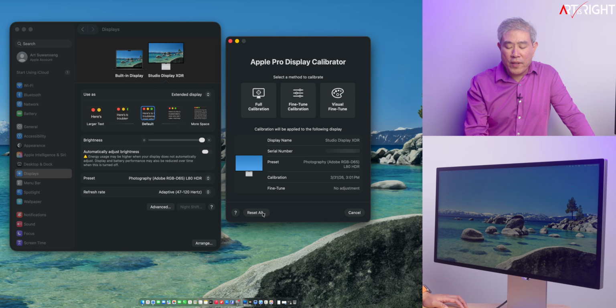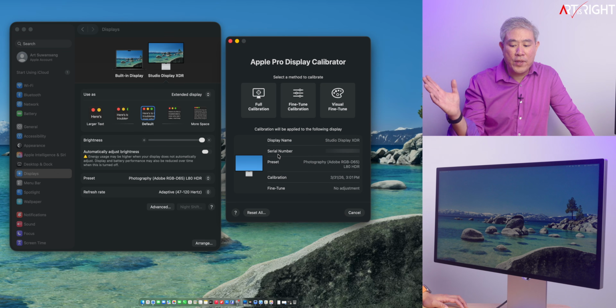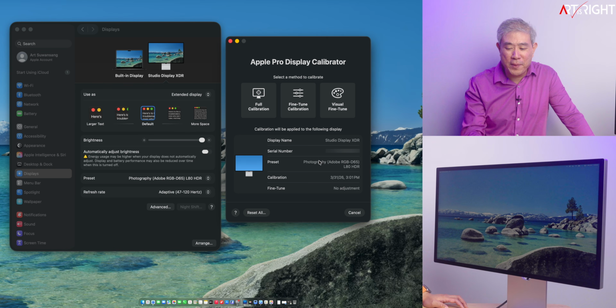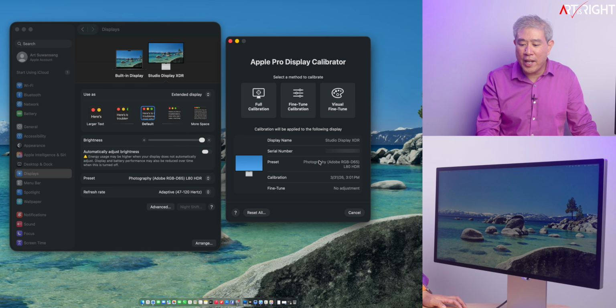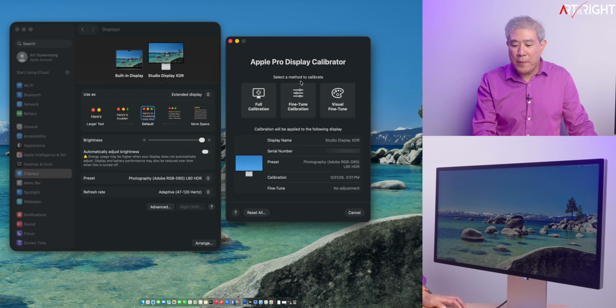At any given point, if I want to reset the entire display, you can click on Reset All and just confirm by resetting all there, and it's going to reset everything back to default. It will remove my full calibration, it will remove fine-tune calibration, all the presets. I still have many more demos to do, so I'm not going to go through that process just yet. At the very top, you have a few methods. Full calibration, we're going to leave that for part 3, but we're going to talk about fine-tune calibration.